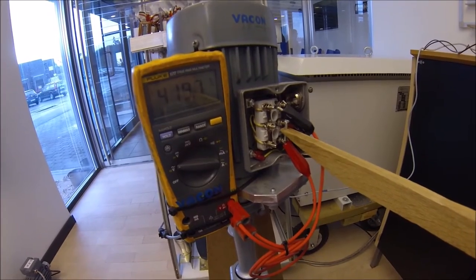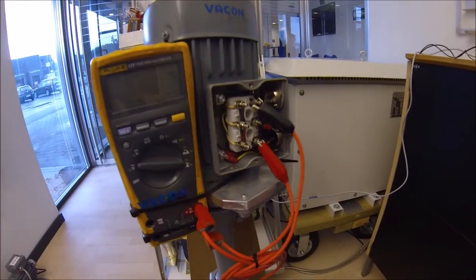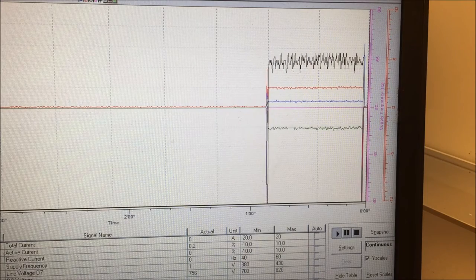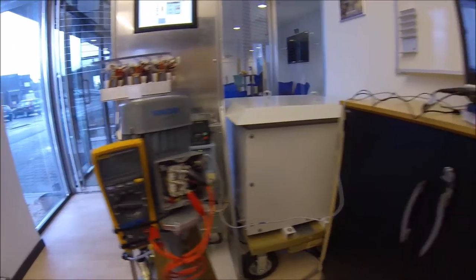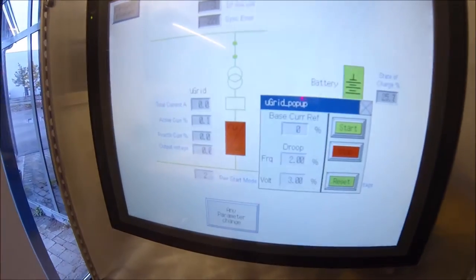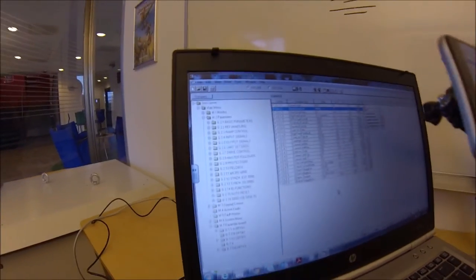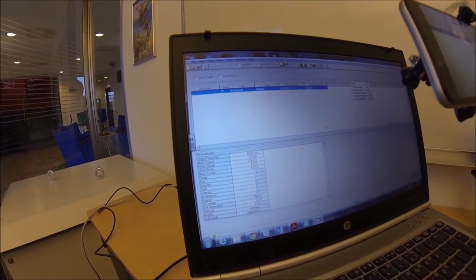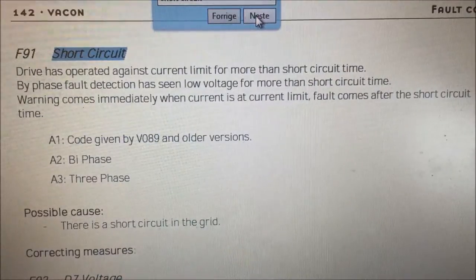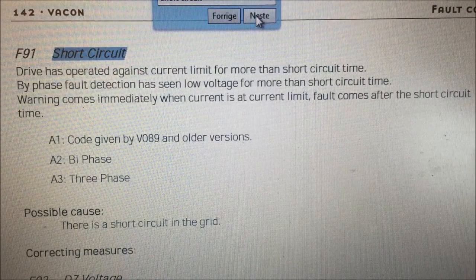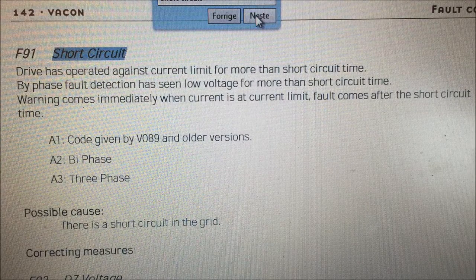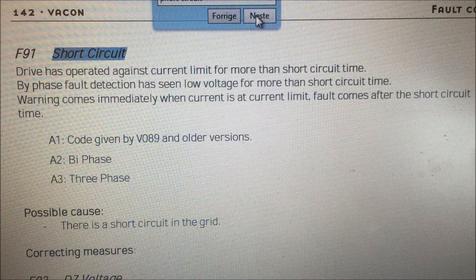Everything stopped. The drive went into a fault and alarm displaying. We've got a fault code F91 that says that there is a short circuit detected in the system and that the short circuit was present longer time than a timeout period.